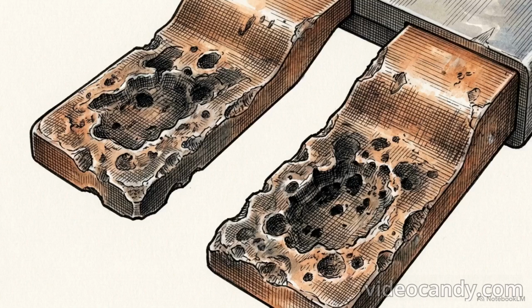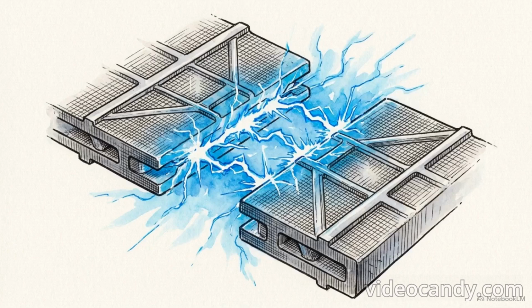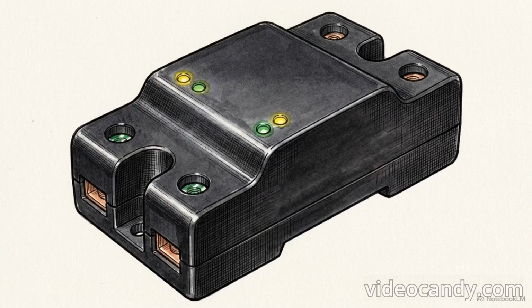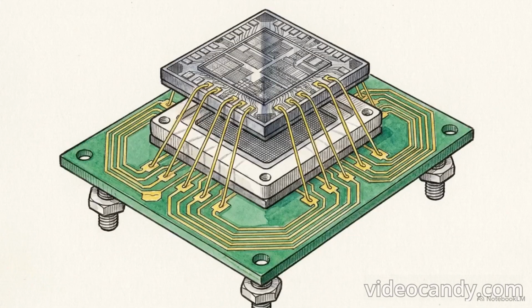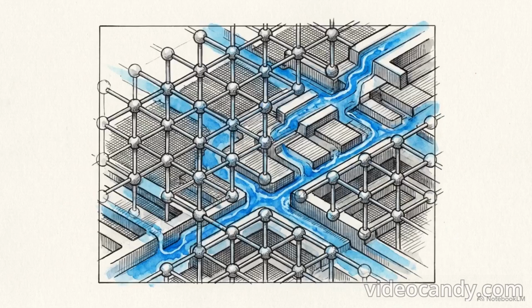Fuses vaporize. MCBs and RCCBs rely on moving iron plungers and mechanical latches. Over thousands of cycles, mechanical parts degrade. More importantly, physically pulling two conductive contacts apart inherently draws an electrical arc for several milliseconds before the circuit is truly broken. The modern ceiling of circuit protection requires eliminating moving parts entirely. That brings us to the solid-state electronic circuit breaker, or E-breaker. E-breakers abandon metal contacts in favor of high-power, wide-bandgap semiconductors. Specifically, they utilize silicon carbide MOSFETs, or insulated gate bipolar transistors, to act as the gatekeepers of the current flow.